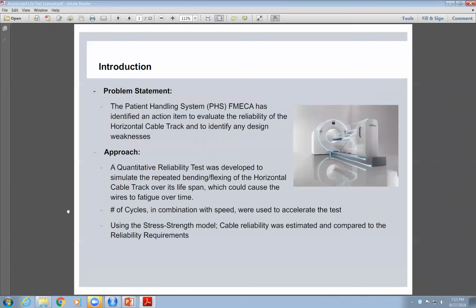We came up with some reliability numbers, and interesting enough, it was actually meeting the reliability requirements. We didn't need to take any additional actions. It's well beyond the reliability requirements we identified earlier. It's not every time something fails, you have to go fix it, by the way. Okay, if it's meeting your requirements that you decided up front, that's great, right? If it's not, then you have to think about it. So based on those calculations, models, again, the application stress and the strength of the material, we said we're good for 20 years. So pretty high reliability numbers for 20 years, actually.